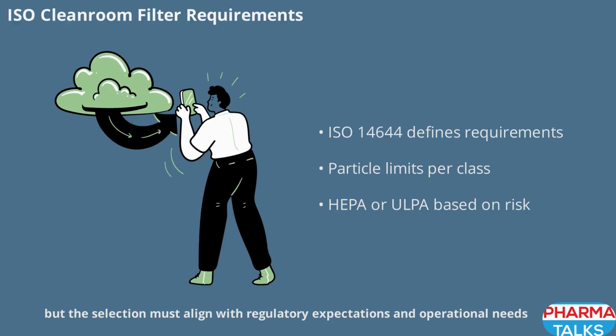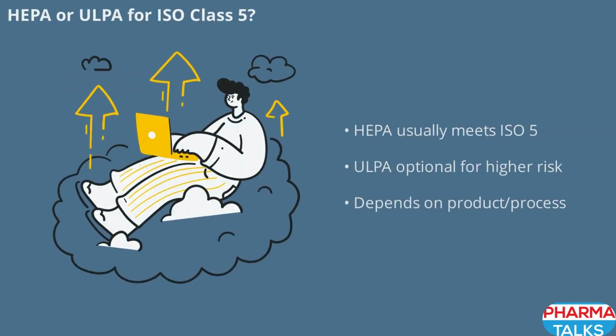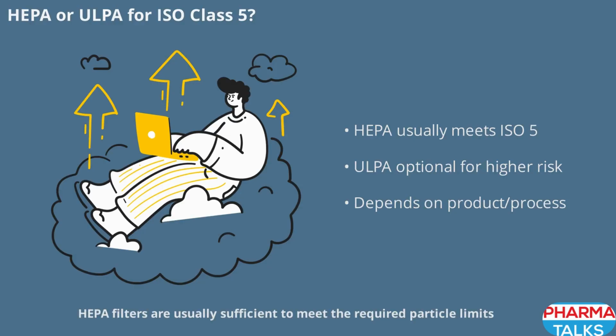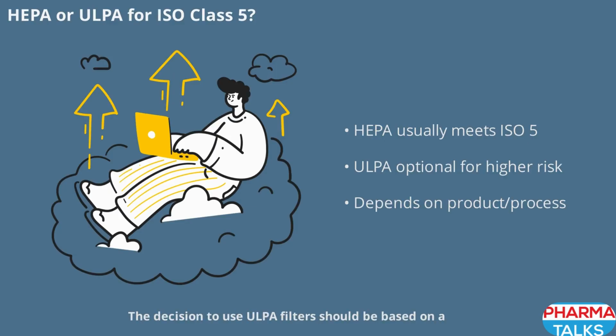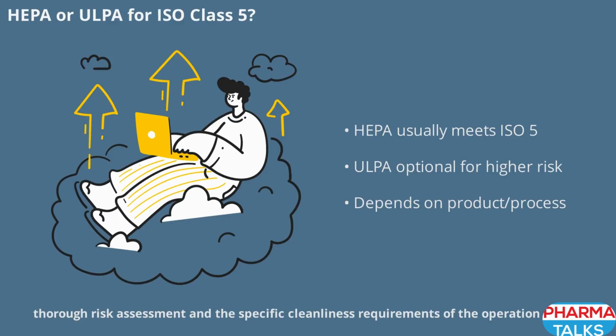expectations and operational needs. For ISO Class 5 cleanrooms, HEPA filters are usually sufficient to meet the required particle limits. ULPA filters are considered optional and are only necessary when the product or process demands an extremely low risk of contamination. The decision to use ULPA filters should be based on a thorough risk assessment and the specific cleanliness requirements of the operation. In most cases, HEPA filters provide the necessary protection for ISO Class 5 environments.